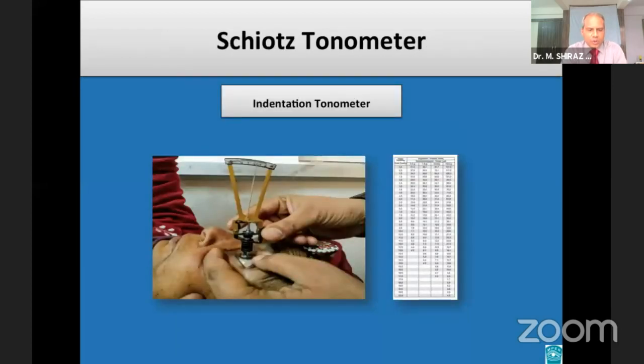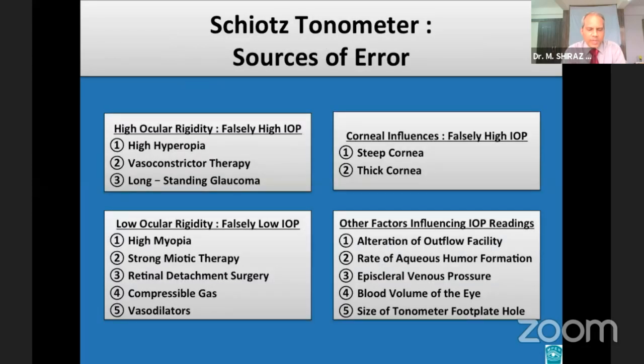The Schiotz tonometer is cumbersome as the patient needs to assume a supine position, but it is affordable, robust, and has no complicated electronics. Therefore, it is suitable for screenings, especially in low-resource and remote settings. However, the Schiotz tonometer does not make as precise measurements as other types of tonometers, as the measurements are influenced by a number of factors.